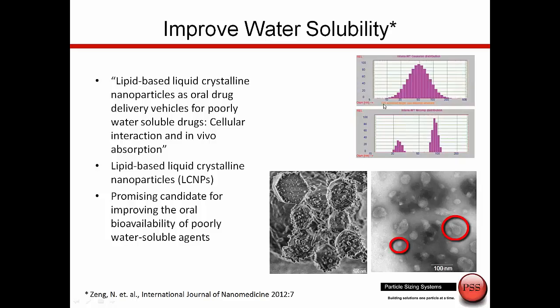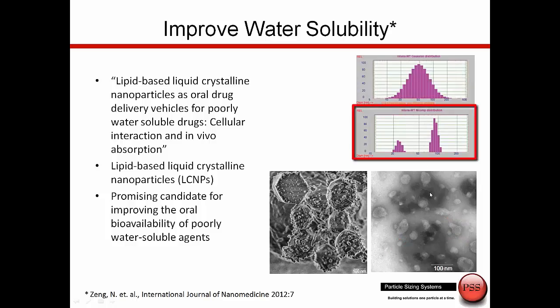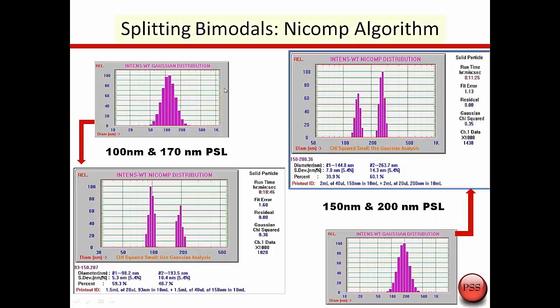When you use DLS and do the measurement, it's actually flagged right on the screen — saying, wait a second, we have a large chi-square, you should switch over to the NICOMP algorithm. Then we see this bimodal distribution, which better describes the size distribution of these particles. That is one of the claims to fame of the NICOMP system.